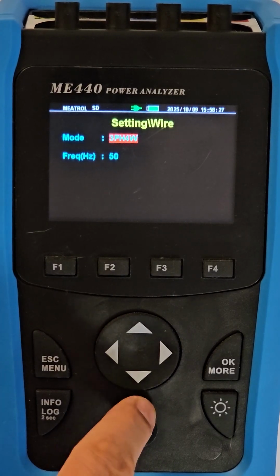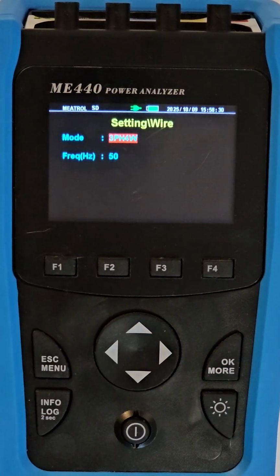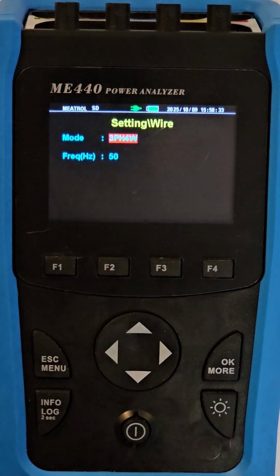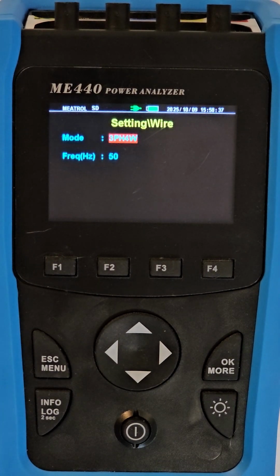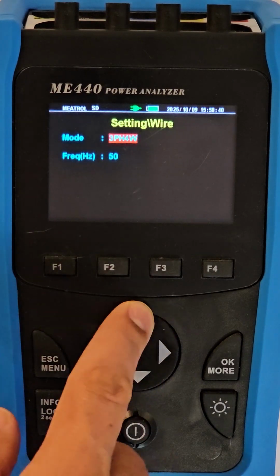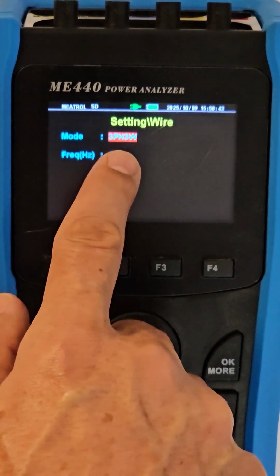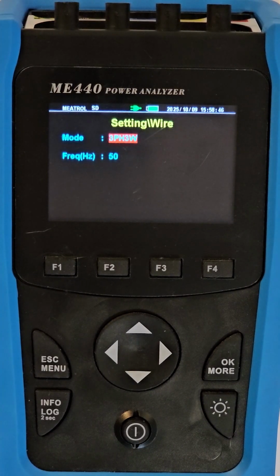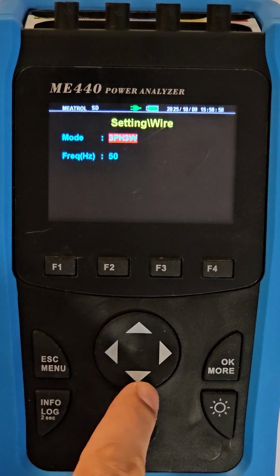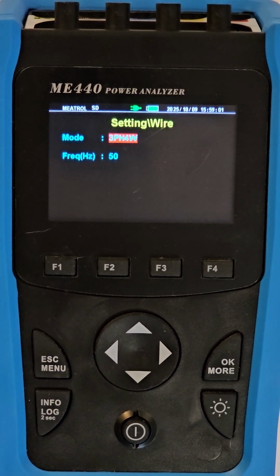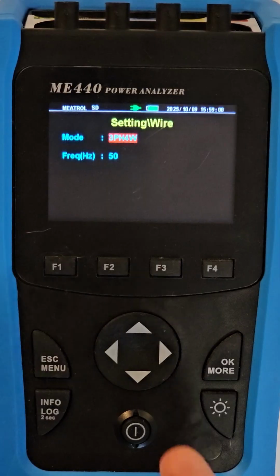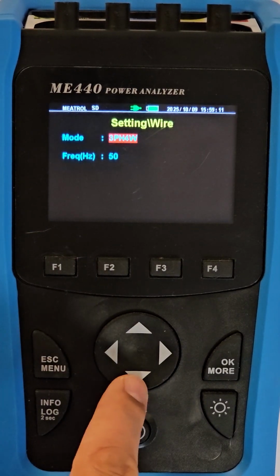So let's start off with 3-phase 4-wire. That's your typical 3-phase installation where you've got your 3 conductors and 1 neutral wire, and then you've got 3-phase 3-wire. That's where you've got just the 3 conductor wires and no neutral. So that's typically on motors and inverters and some other devices that just use a balanced 3-phase and don't have a neutral wire. Okay, but for most 3-phase installations you'll select 3-phase 4-wire. It's important to select the right type of mode, otherwise it will give you incorrect data.